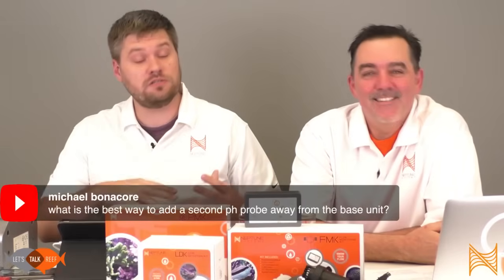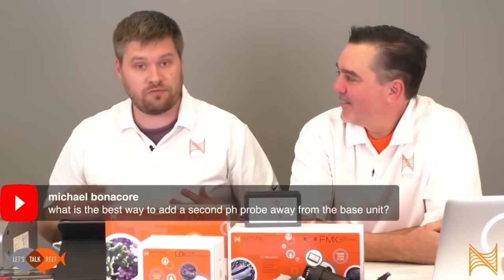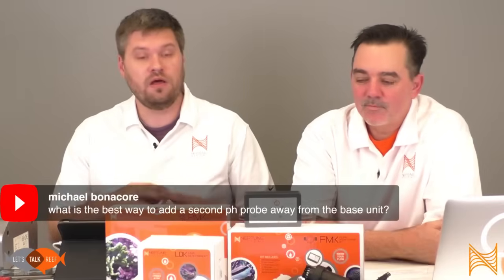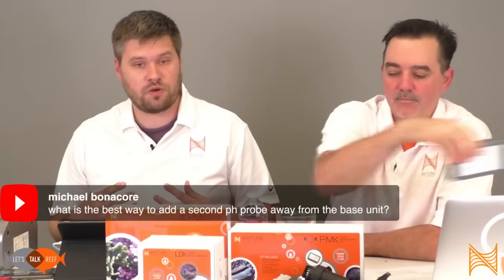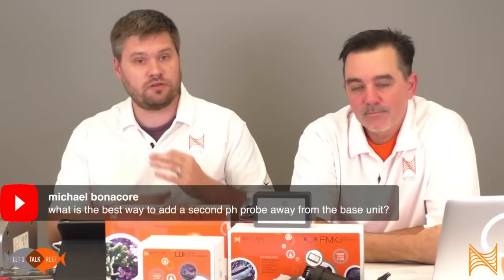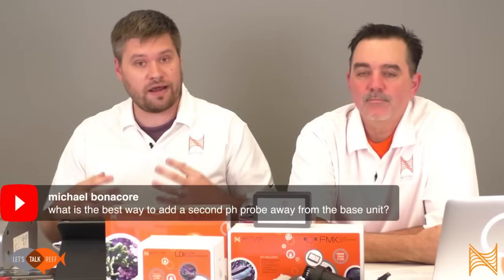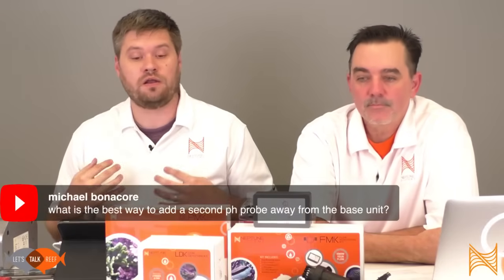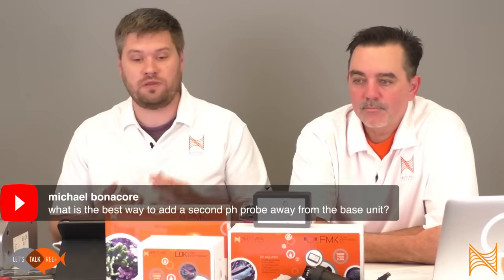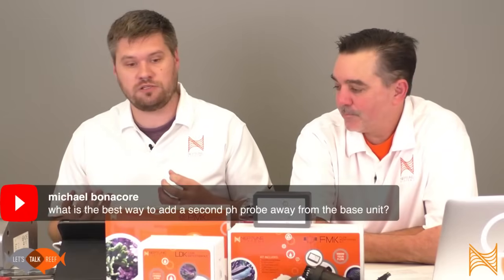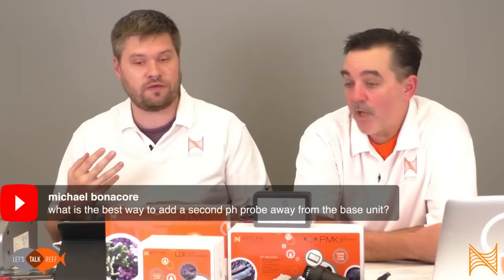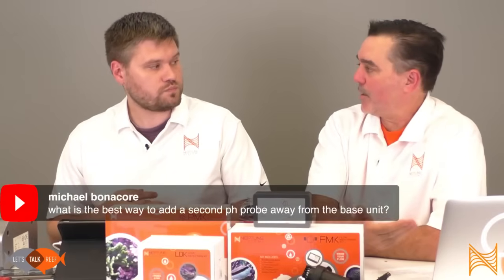What you want to do is get our 15 or 30 foot Aquabus cable, the male cable, and one of our PM1 modules. With that PM1 module, you connect it up right next to where you need to monitor, and you won't have any issues with EMI or signal degradation. You can also daisy chain another one or two modules on there easily.